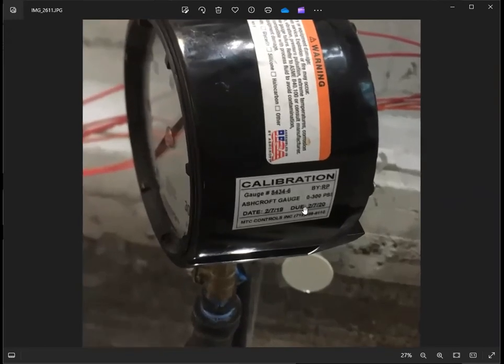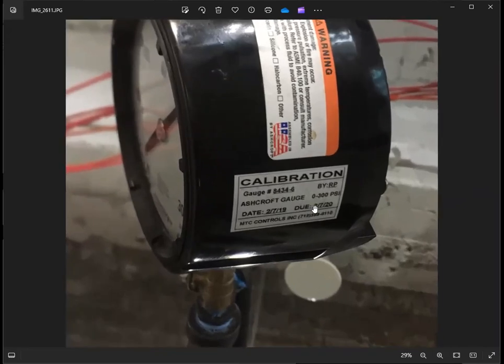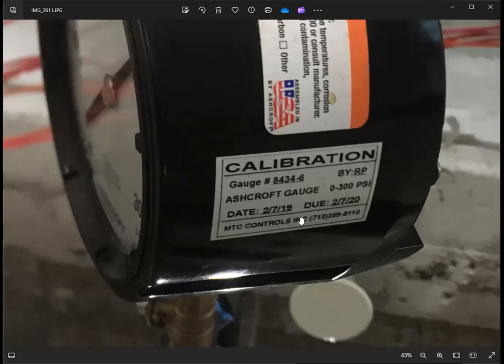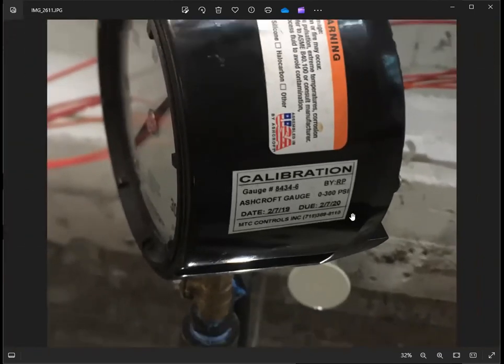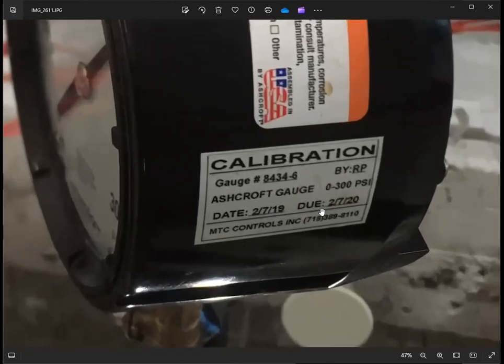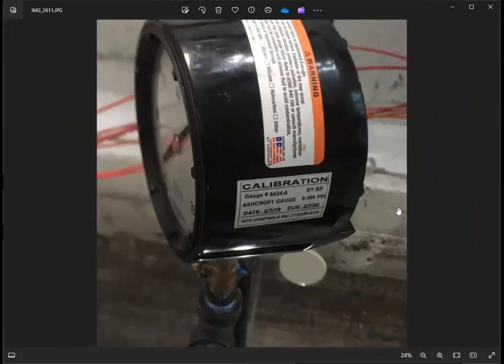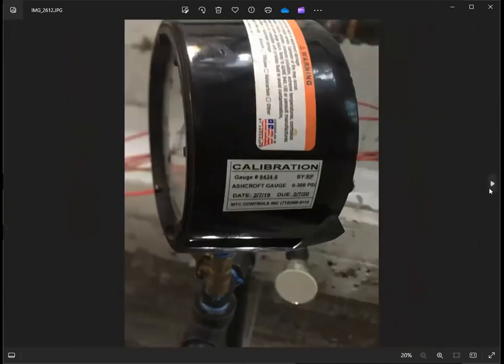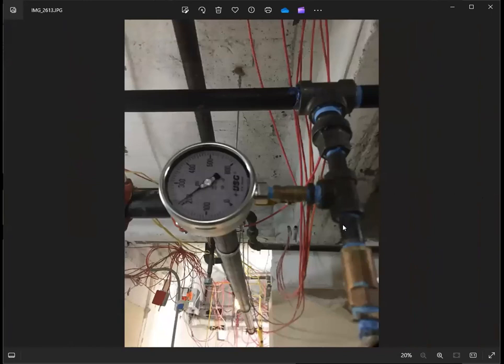Also take note of the pressure gauge calibration. We need to test the system with a calibrated gauge, not a non-calibrated gauge, because this will indicate if the pressure applied to the system is accurate. So take note of the date when it was calibrated and the due date. On the day that you're doing the inspection, the calibration cert of the pressure gauge you're using for the test should not be past due. And yeah, take a photo of the whole assembly that you were testing.